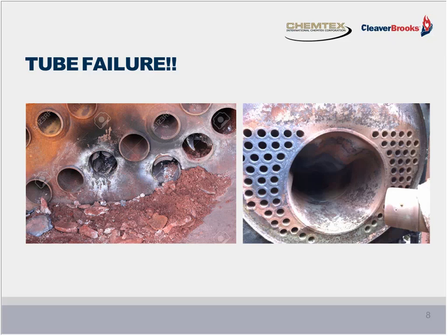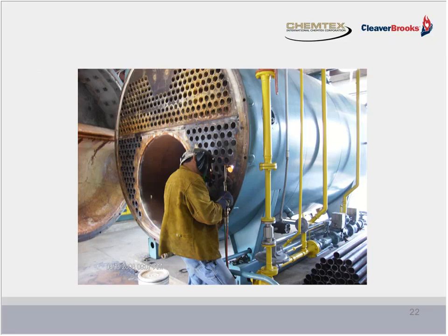And it all leads to very costly repairs and downtime, which in some situations can be more expensive than the repairs themselves. The downtime can. For instance, here is a 500 horsepower fire tube boiler, which is requiring all the second pass tubes be replaced because of excessive scaling, which caused the tubes to overextend, tearing them loose from the welds to the tube sheet, which then caused excessive leaking.